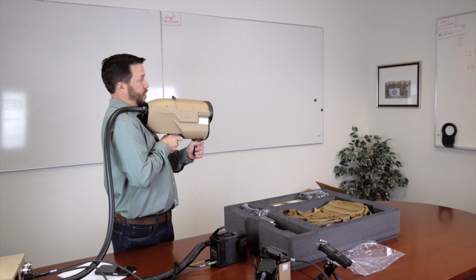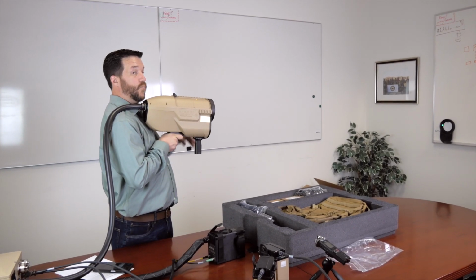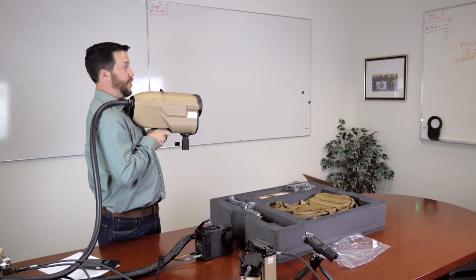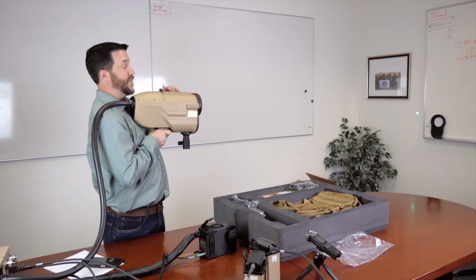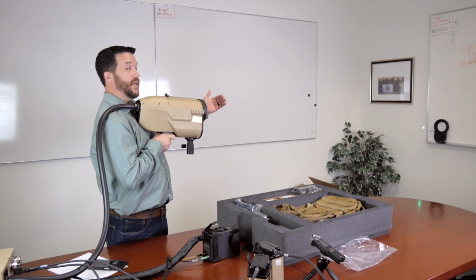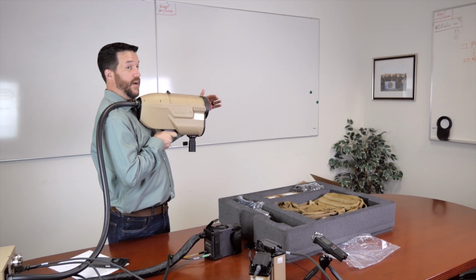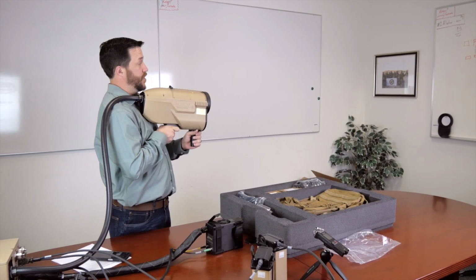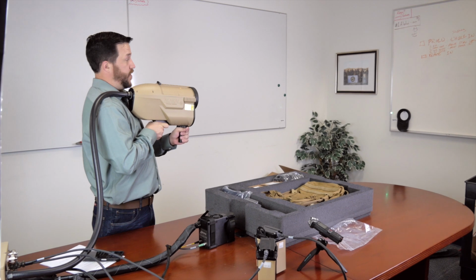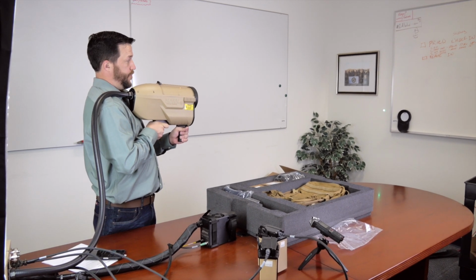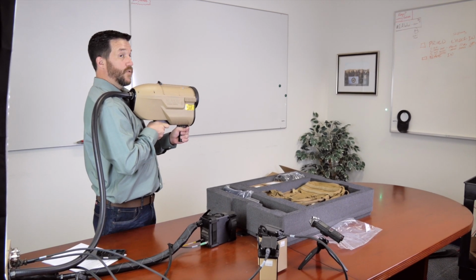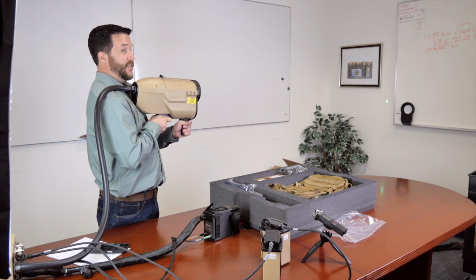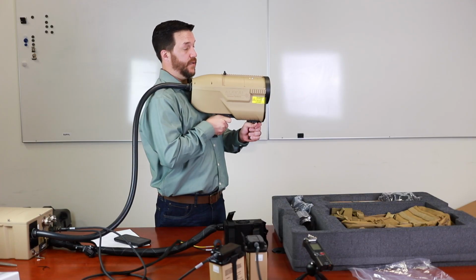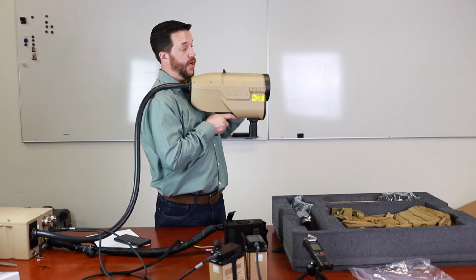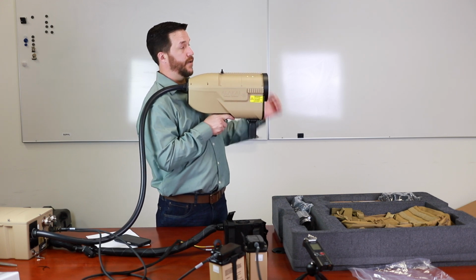Pulling the trigger slightly in will send the motor to its focus location, so it's not sampling at your range anymore, but a designated spot in between you and 5 meters. That's why you need the 5 meters. So once the motor has stopped moving, finish pulling the trigger, and the blue LED will start. You take 5 seconds worth of data on the self-test. You'll hear your audible alarm and your green LED indicate.